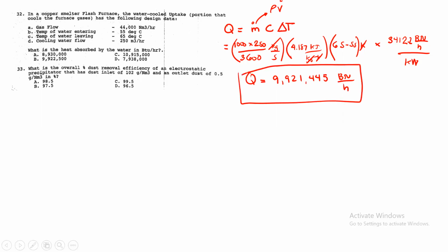So next, 33. What is the overall dust removal efficiency of an electrostatic precipitator that has a dust inlet of 102 and an outlet dust of 0.5, in percent? So paano itong 33? Para makuha natin ang overall dust removal efficiency: dust inlet minus dust outlet, divided by dust inlet. So equal yan sa 99.5%. So the answer is letter C.